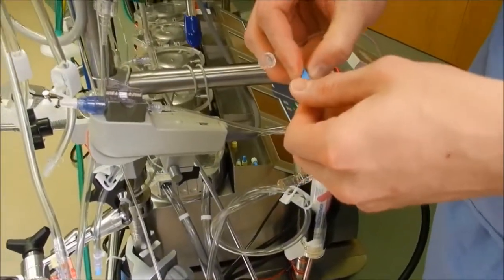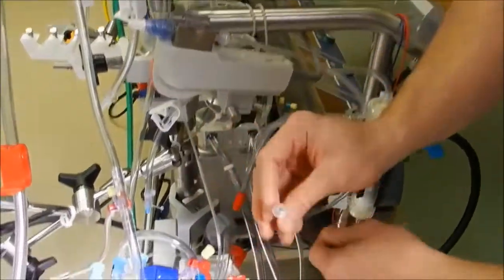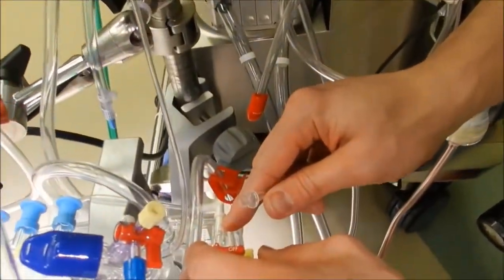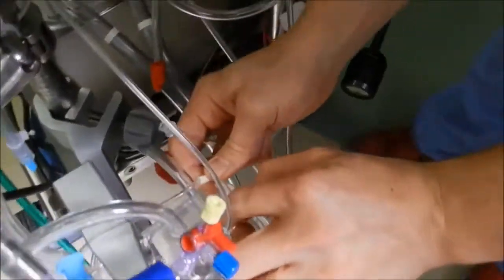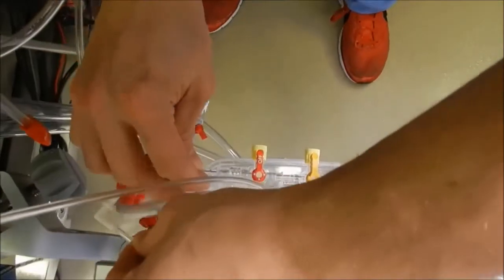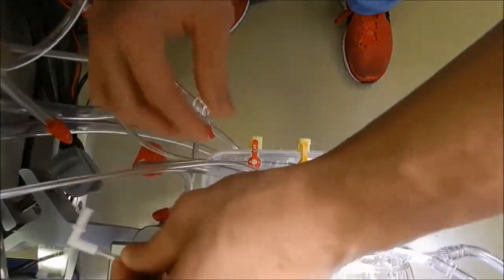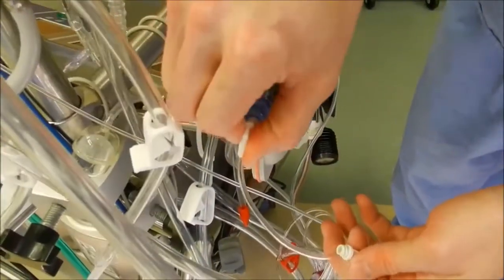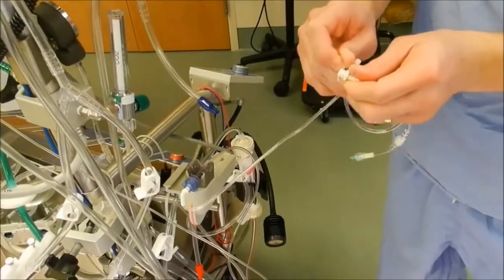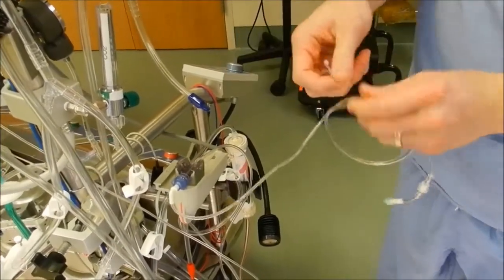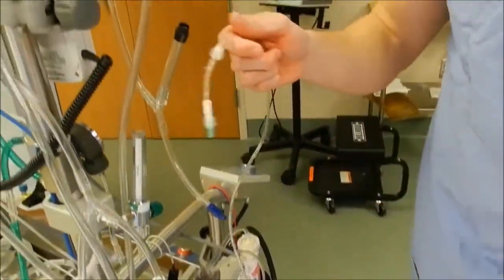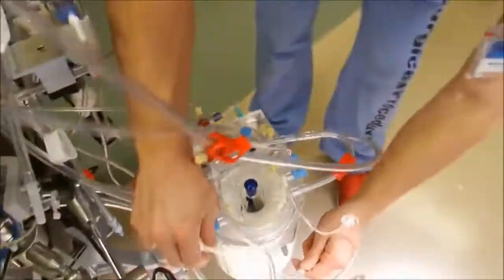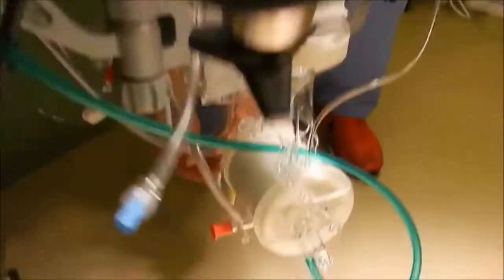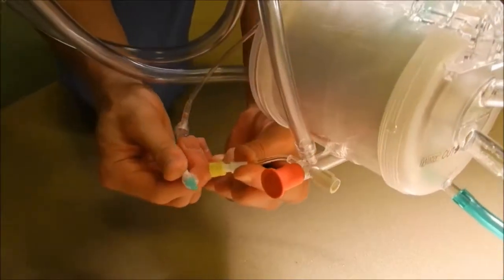Again, we'll save. And then this part gets connected to our arterial end of the manifold. Be careful not to contaminate this end, as this will move to the top of our CDI, or to the inlet of the CDI. So right up here. When we have our sampling, our CDI will measure off of our oxygenator. So this connection here gets moved down to our outlet of our oxygenator. So the pigtail that comes off that outlet.